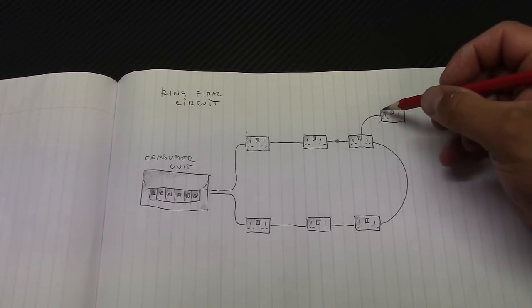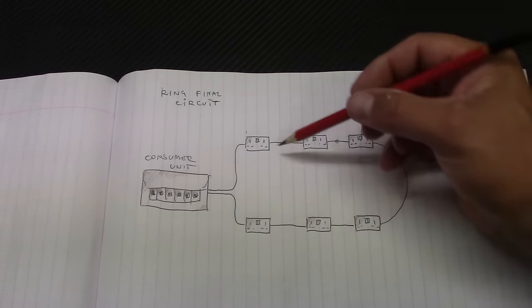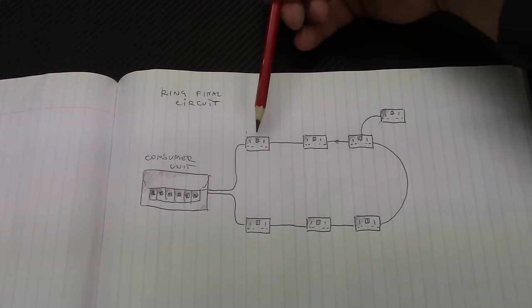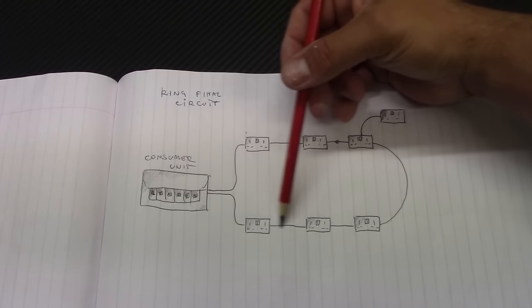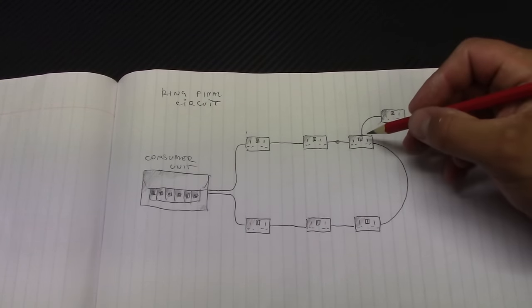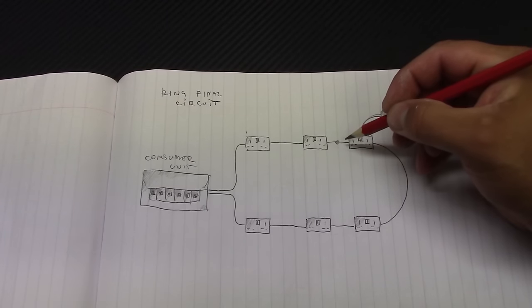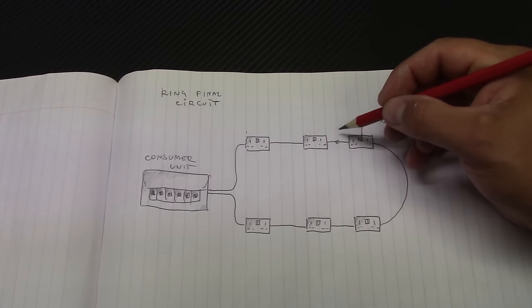The number of spurs, unfused spurs, is limited by the number of the sockets on the ring. So in this ring we've got six sockets on the ring. So unfused spurs we can have only six. So it doesn't matter if it comes from the socket outlet or from the junction box on the cable.